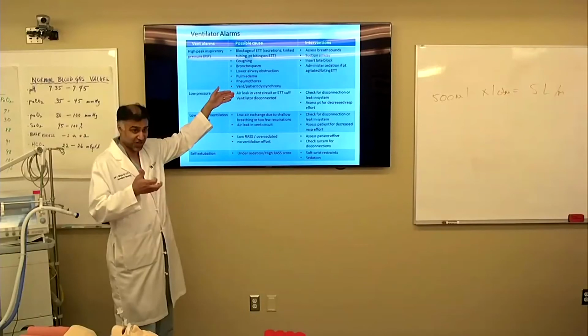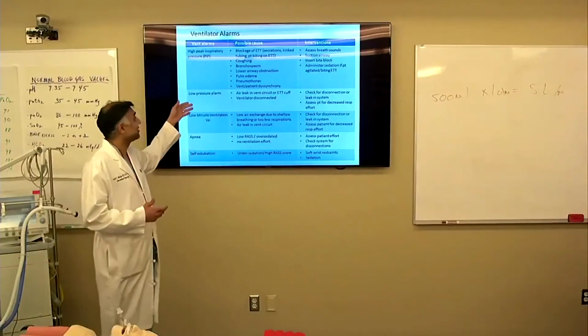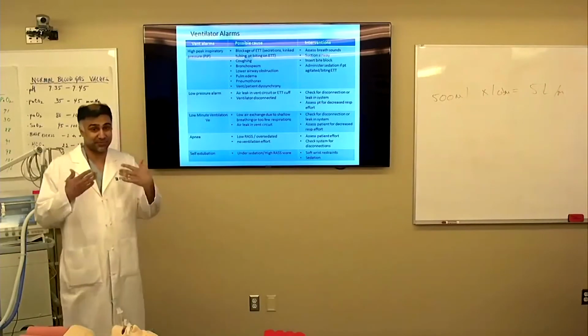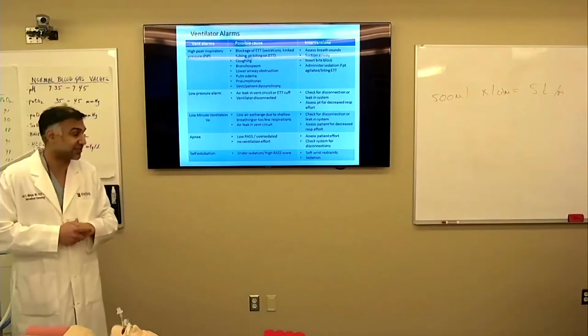So, low pressure alarms. There's a couple of things we worry about. You worry that the actual volume is not being delivered, that you're not getting the peak pressure and the plateau pressure you're hoping for. One, you look for a leak in the circuit, and honestly, you look to see if the ventilator is disconnected from the actual ET tube, which is not that uncommon. So assess your system and your circuit, make sure there's no issue, and also make sure that the low pressure isn't because the patient isn't breathing in or there's something abnormal in the settings of your vent.